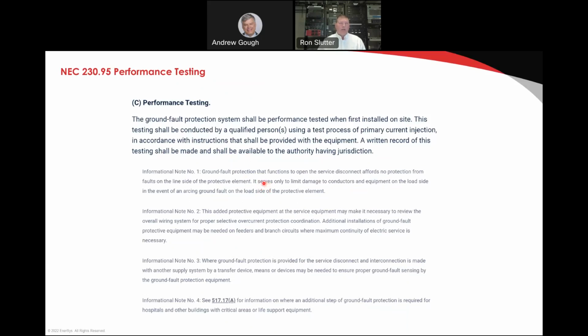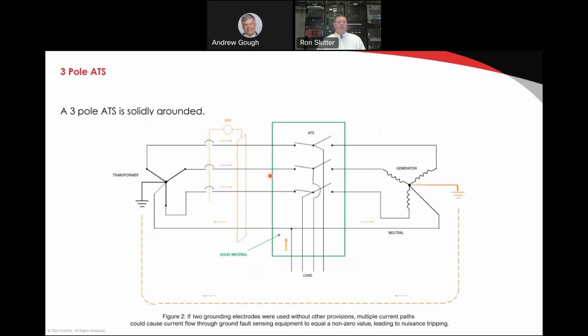I'm really not going to get into the weeds with that, but basically you need a power study for your system. And that's basically engineering. You have to have a system engineered when you get to this kind of level of system. So here's an example of a 3-pole ATS. You can see here we have a transformer, we have a ground fault circuit breaker on a 3-pole system. And if we were to do that, there's the chance that with a solidly grounded system, we can have circulating ground current that can produce a nuisance trip environment.